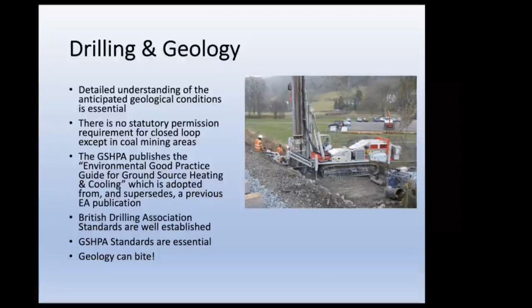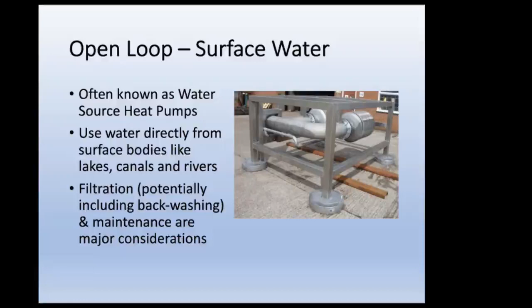Open loop systems are taken from lakes, canals and rivers. We've got to remember that we don't particularly want the source water to go through the heat pumps - we would prefer plate exchanges in between. So if there is any cleaning to be done of any biological growth, that can happen within the plate exchanges and not the heat pump.